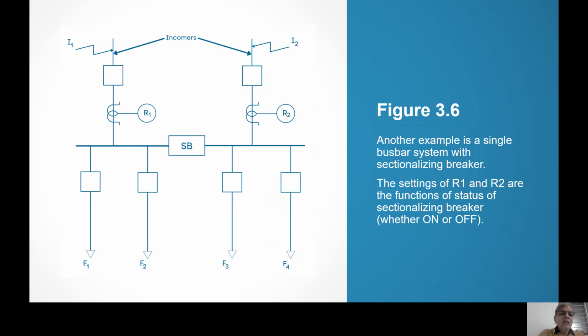Next possibility of dynamism. What is the next possibility? I have got a single bus system with a sectionalizing breaker. I've got two incomers, I1 and I2, and four outgoing feeders, F1, F2, F3 and F4. Now what happens if the sectionalizing breaker is on? Then current will come from I1 and go to F1 and F2. But the requirement at F1 and F2 is less. F3 and F4 require some more current. So current will pass through the sectionalizing breaker and go to F3 and F4 also, right?